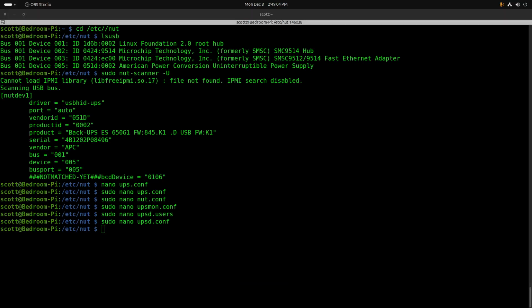When I edited that user file, I mentioned those instant commands. The instant commands can perform things like battery test, turning off the UPS load, restarting the UPS, calibrating your battery if your unit supports that, shutting down particular UPS outlets if your unit supports that, and enabling and disabling the beeper as I showed you in the demo for the PeaNUT software.